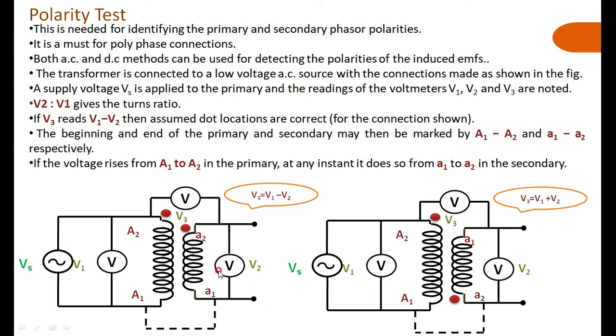This is about the polarity test. Our main objective is to mark the highest potential terminal of the primary and secondary windings with dots, by measuring the voltage between two terminals. If the voltmeter reads the difference, the terminals are at the same potential sense; if the voltmeter reads the sum, then there is a change in the dot connection — they are exactly opposite.